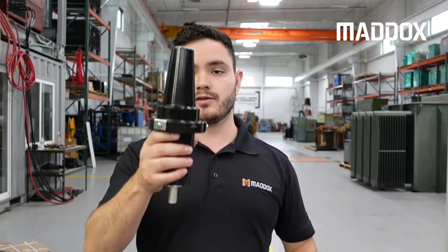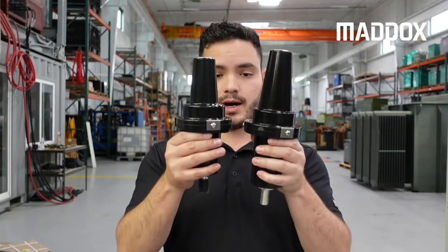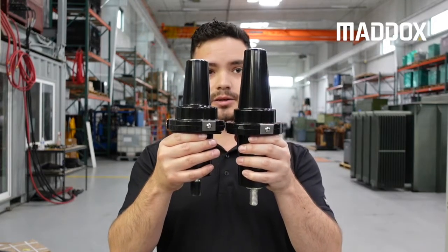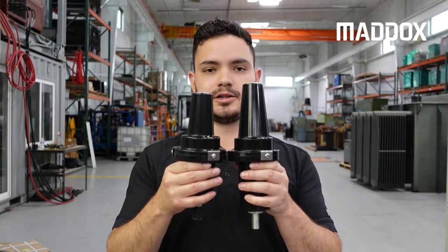So you've got your 15/25 kV deadbreak bushing and then your 35 kV deadbreak bushing. These are not color-coded once you get up to 600 amp, but you can tell the difference because the 35 kV is a little bit bigger — higher voltage requires a little bit more insulation. That's the only way to tell the difference between these two.